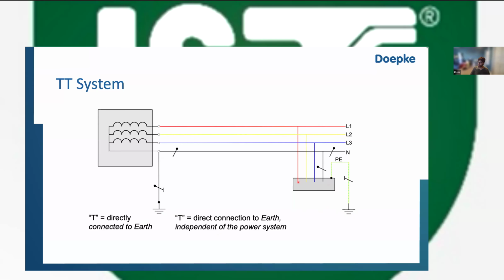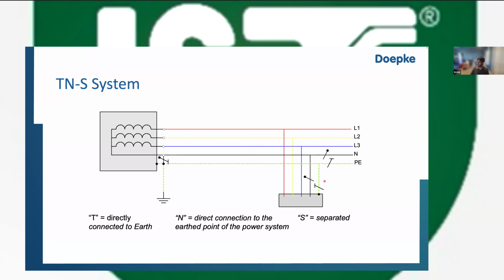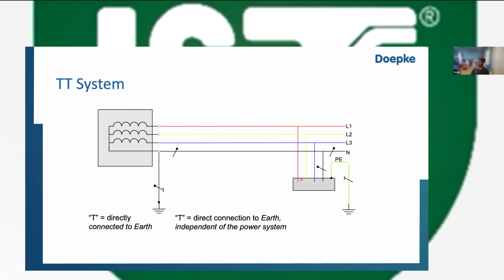So in the event of a fault of negligible impedance between the line conductor and the protective conductor of the body of the equipment, unlike in the TNS system or any other TN system for that matter of fact, you will have a very small amount of current. So in this case, you may have thousands of amperes. In this case, you may have 1 or 2 amperes.